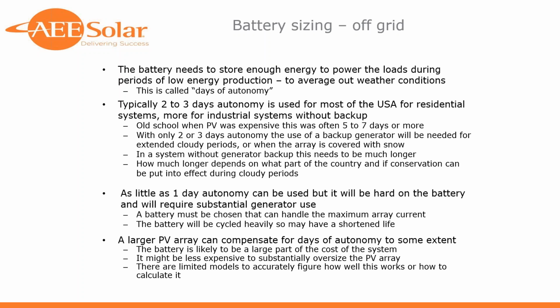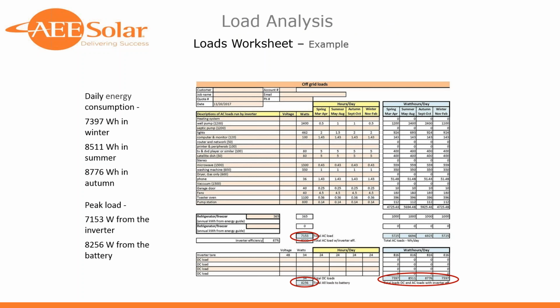Okay, so the first thing, as Josh said earlier, if you're designing a system, you need to determine what your loads are for the system. And this might be a little bit small to see, but basically what you're doing here is listing your loads, how many watts they take and how many hours a day you're likely to run them, broken down by season, of course, because generally there's a lot less sun in the winter. Sometimes your loads are larger in the winter, although in the south part of the country, maybe the summer loads might even be larger. So you have to look at it seasonally also.